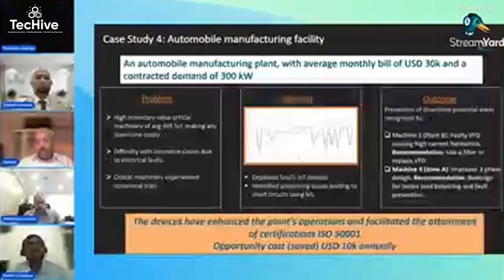So that's when our solution was deployed. It was able to identify what was happening in that assembly line - specifically a couple of VFD machines which were causing harmonics, or back currents, into the entire panel, which affected that panel and got it downgraded. That's when the assembly line had to go down and they had to fix the problems.